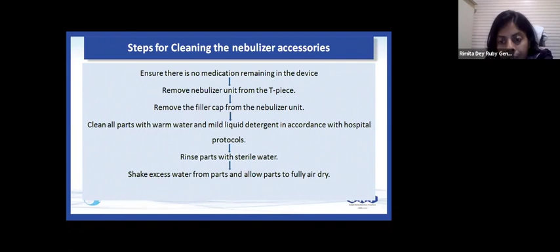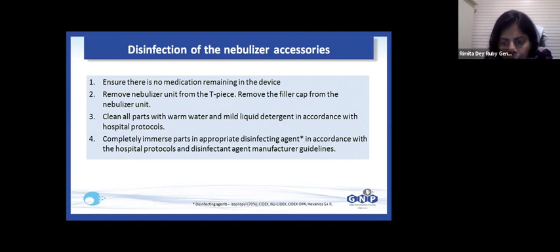Disinfection of the nebulizer accessories. Ensure that there is no medication remaining in the device. Remove the nebulizer unit from the T-piece. Remove the filler cap from the nebulizer unit. Clean all parts with warm water and mild liquid detergent. And completely immerse parts in appropriate disinfecting agents in accordance with the hospital protocols and the manufacturer's guidelines.